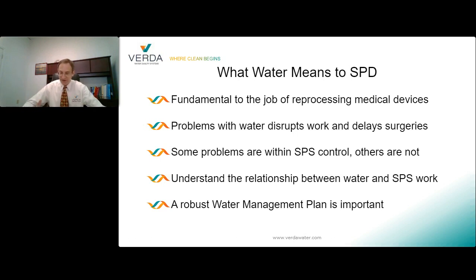So issues with water can cause insufficient decontamination or sterilization of instruments. When we talk about water quality, we're also talking about adequate water pressure and temperature. So low water pressure, like momentary dips or spikes in water pressure, can cause equipment faults. Likewise, if the water is too hot or too cold, this can also cause faults. Faults mean restarting or repeating the cleaning process, resulting in SPD throughput hits.